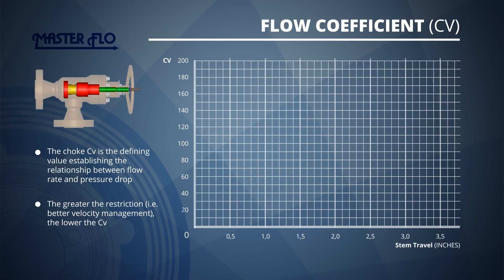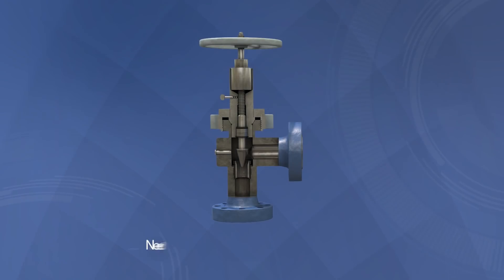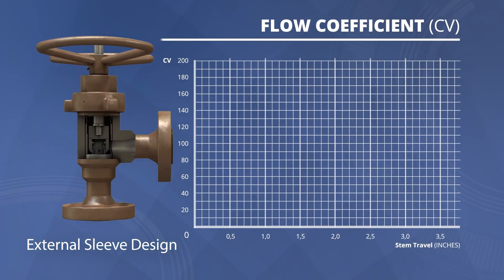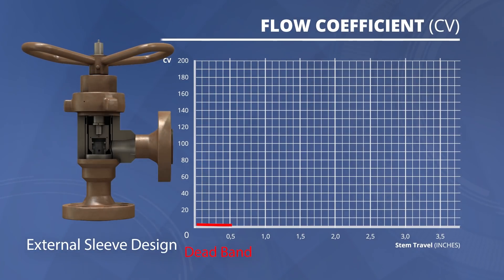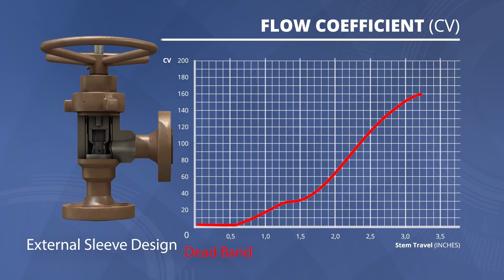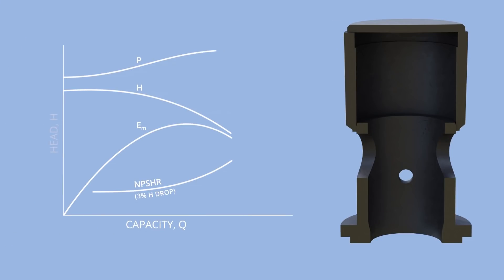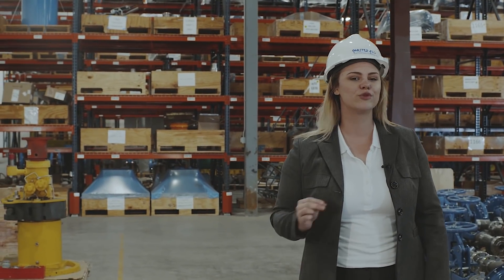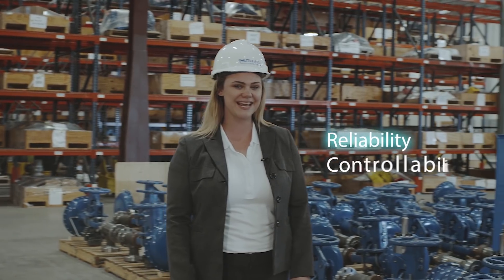A greater restriction provides better velocity management but lowers the flow capacity. When the seating area is close to the throttling area, erosion issues may occur, as frequently happens with the needle and seat valve. MasterFLOW solved this issue by incorporating a dead band area in the design of the external sleeve and cage choke valve. The dead band ensures that the throttling area is far from the seat, resulting in an area of zero flow. MasterFLOW's custom trims can be designed for a specific pump curve, providing high loss coefficients at low flows and low loss coefficients at high flows, eliminating the need for parallel valve operation and reducing maintenance while increasing reliability and controllability.